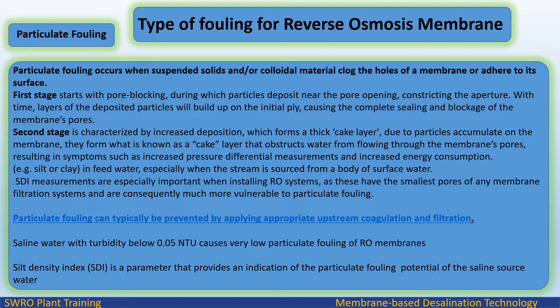For example, silt or clay in feed water, especially when the stream is sourced from a body of surface water. SDI measurements are especially important when installing RO systems, as these have the smallest pores of any membrane filtration systems and are consequently much more vulnerable to particulate fouling. Particulate fouling can typically be prevented by applying appropriate upstream coagulation and filtration. Saline water with turbidity below 0.05 NTU causes very low particulate fouling of RO membranes.